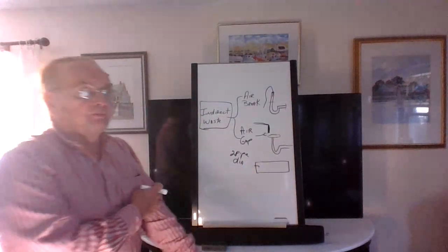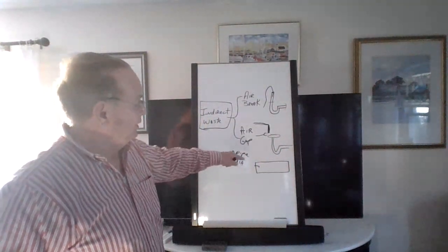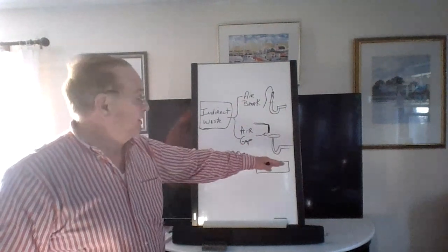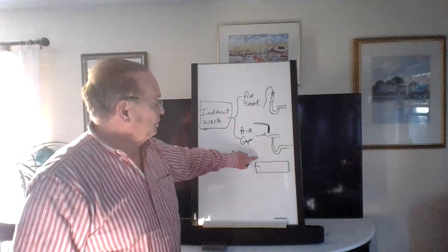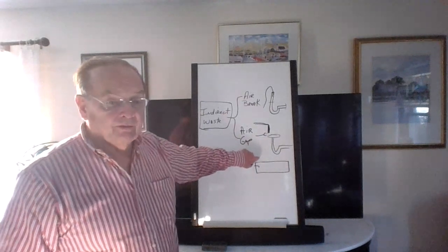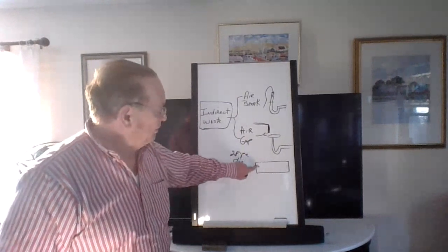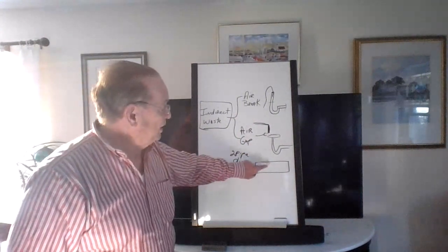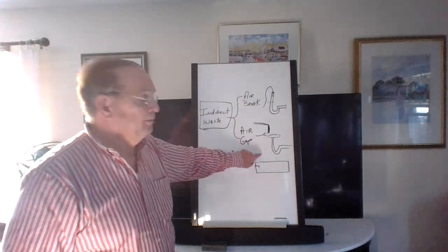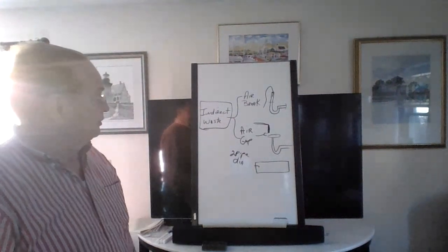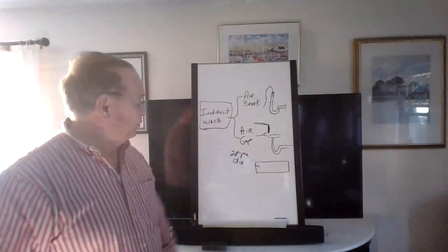I don't know if you guys have been still putting these in, but this piping would leave the faucet and would run over to the wall. This would be like in a box. You just drop the tub in, and this will go over to a backflow preventer in the wall, like a vacuum break, excuse me, and then over to the faucet and come out here. Okay, so the water could not siphon out of here and back into the system. It would have to go through that vacuum valve.